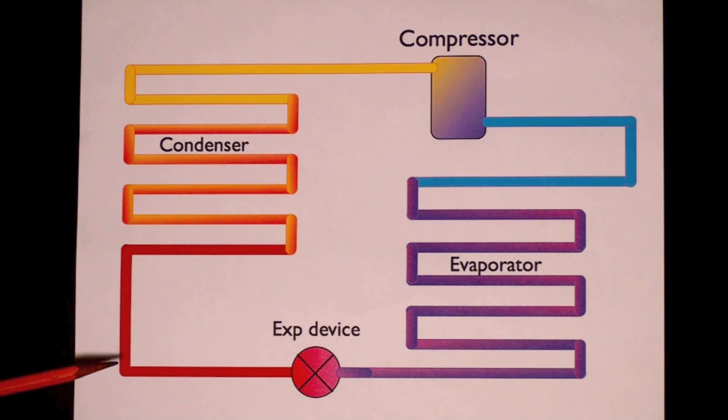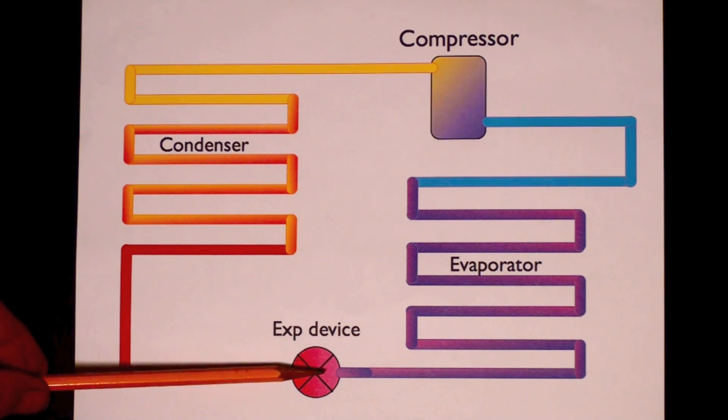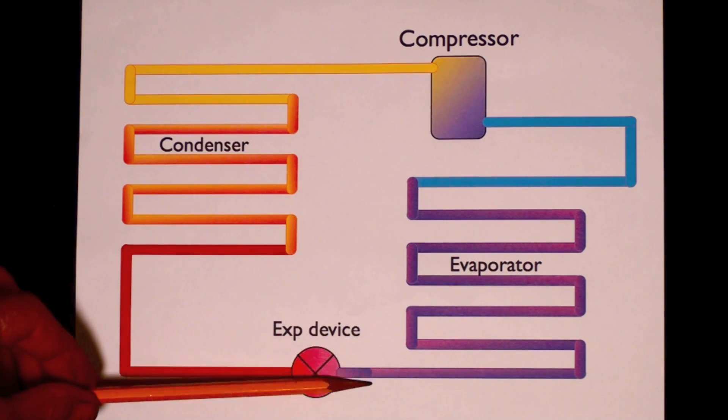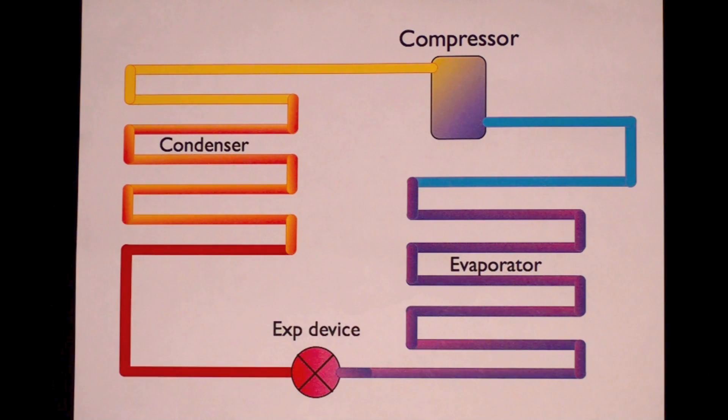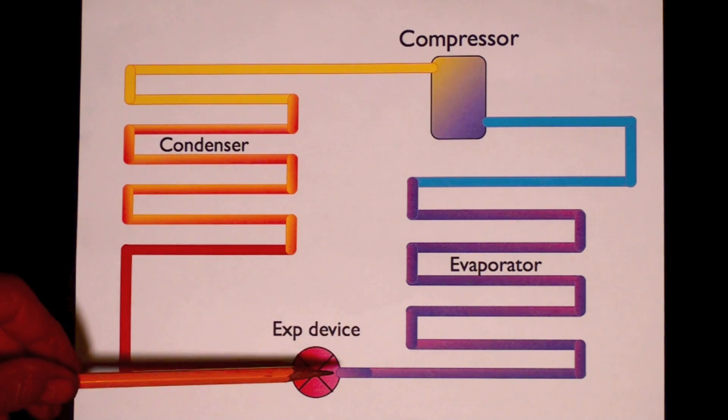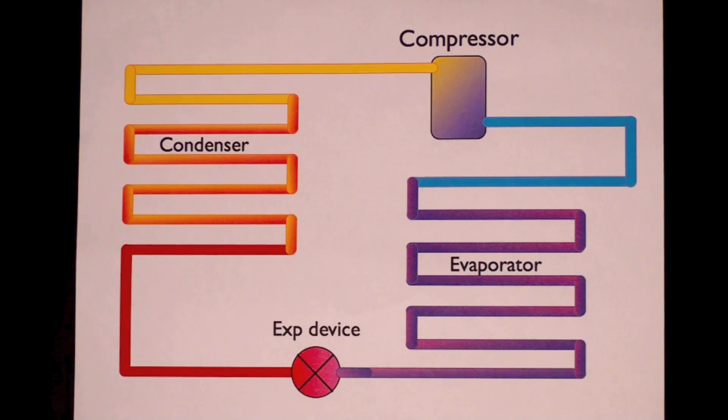So it passes through the liquid line, hits the expansion device, and then the expansion device, because it's a limiting device, it could be just a small hole, the pressure on this side is going to be much higher than the pressure on this side. So the refrigerant passes through here. Its pressure drops from the condensing pressure temperature to the evaporating pressure temperature.